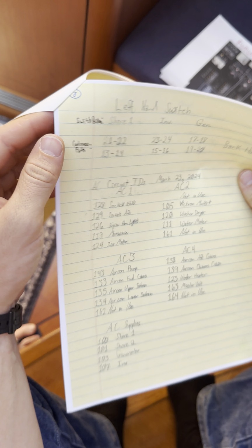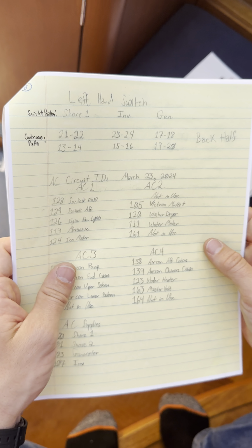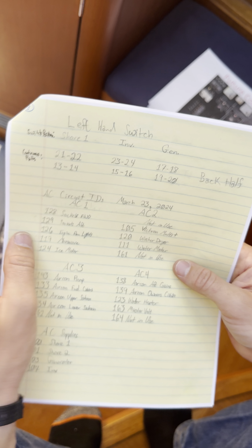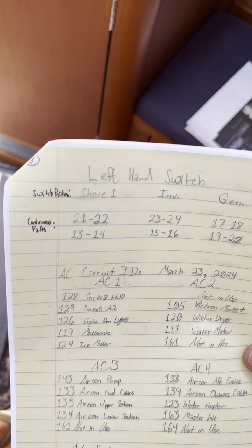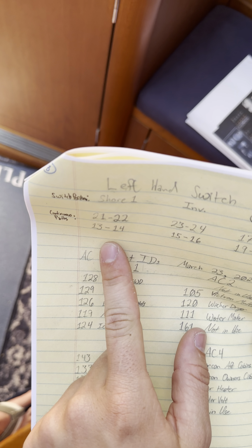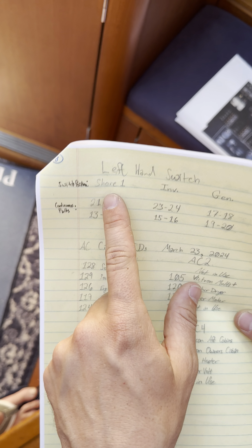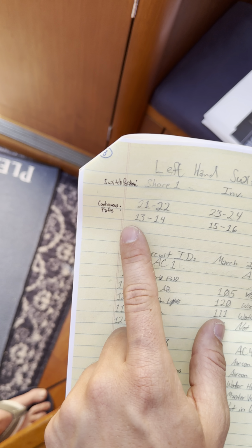Then the only other major piece of information in here that I think will be helpful for Sam, potentially, would be this section, which I got from ringing out the switch in all of its different positions, with the breaker ties all removed.